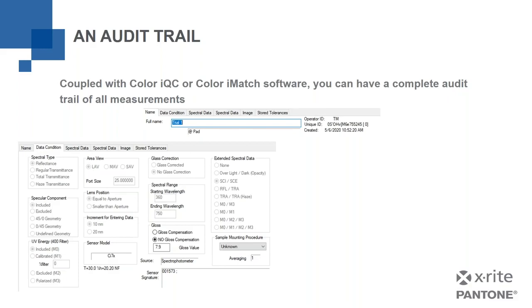Now, those are being recorded not of the surface of the sample, but that's being recorded inside that drawer I talked about earlier in the device. So we have a sensor inside there, helps us know what temperature your calibration media is at to ensure very accurate calibration. But we also record it at every measurement. So it was taken at 30 degrees C and 20.2% relative humidity. So just knowing that, maybe I see, oh, you're getting a different result than I am, but your temperature says 30 and mine says 20. That might give us a clue as to why.